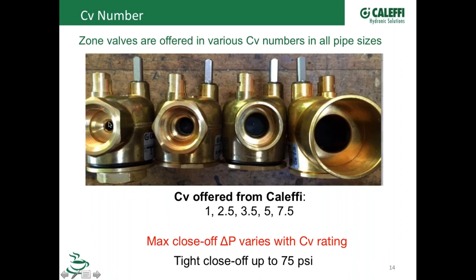What I would caution the repair guys about, if you go out on a job to replace the zone valve and you're on a commercial building, just be aware of that CV number. If you put this valve on that application where they've got a high pressure pump down in the basement, you're going to get bleed through on that valve. And you say, well, I've got a bad zone valve, it's not shutting off tight. Well, it might be misapplied. So that number is important, especially when you start looking at jobs that have high pressure circulators in the building somewhere. So that's in a nutshell the difference. Notice too that this 1.25 inch valve is a 7.5 CV valve.